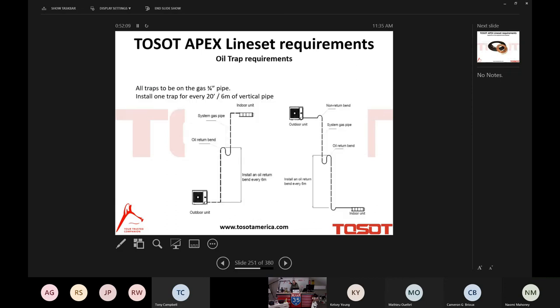When we talk about 49 feet of vertical rise, if you will, between the indoor and outdoor unit, in that situation, we would have to trap twice because we're going to have to oil trap. This is only on the gas side. We're going to trap every 20 feet. So if you were at the vertical maximum of 49, you're going to have two traps there, baby, right? Just makes sense. Simple math.